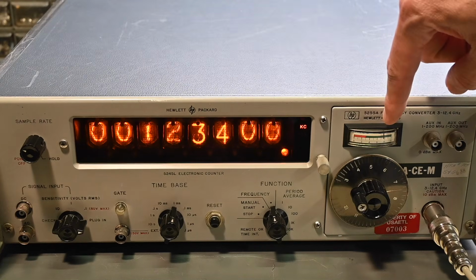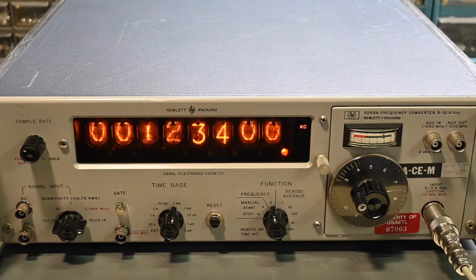And lots of signal indication on the meter, way over into the green scale. Now this is sitting at 0 dBm for the input. You can go to a maximum of plus 10 dBm. Now this should be sensitive down to -7 dBm. That's a specification, but it should probably go lower than that. So HP is pretty conservative on the ratings.